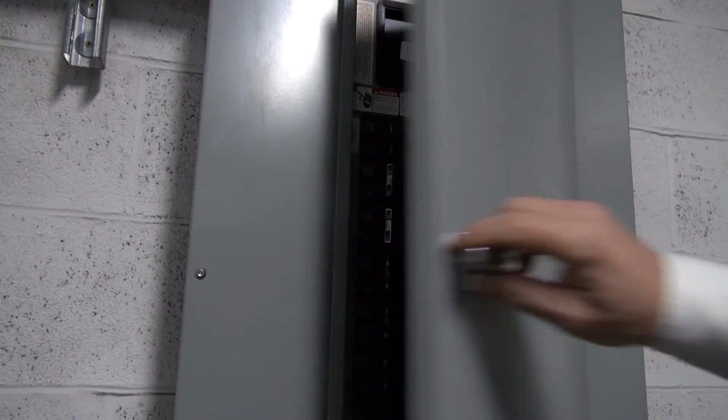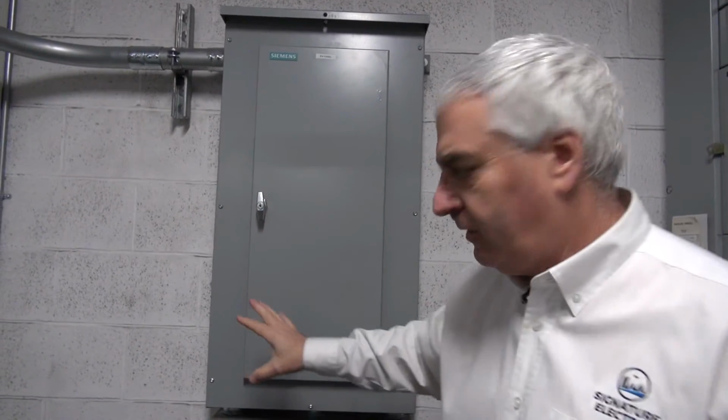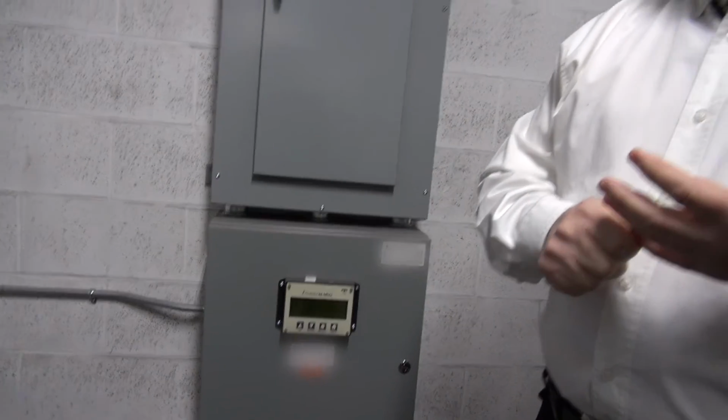valuable information. In part, the reason for doing this would be, if I was simply to put in this panel with no control, I would have to assume that every one of the chargers was on all the time at the same time. And I would have been limited to about 5 or 6 40 amp breakers in the panel. And at that point, I would have a risk of blowing the fuse.